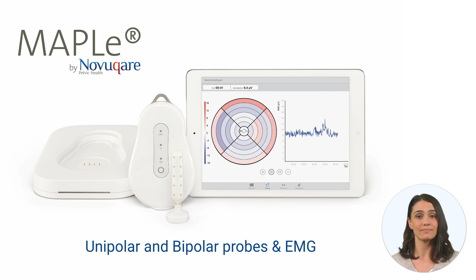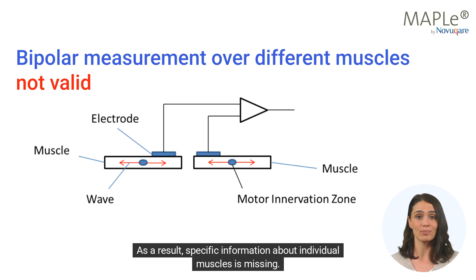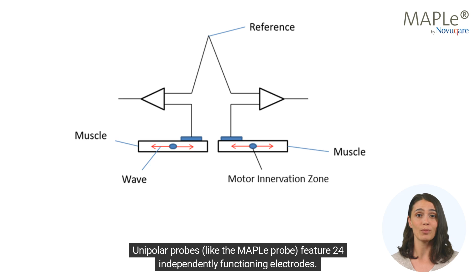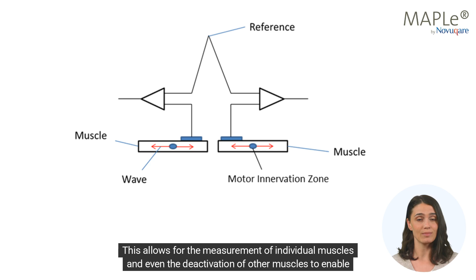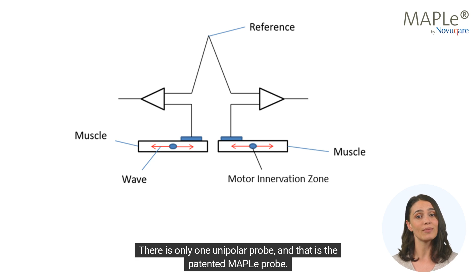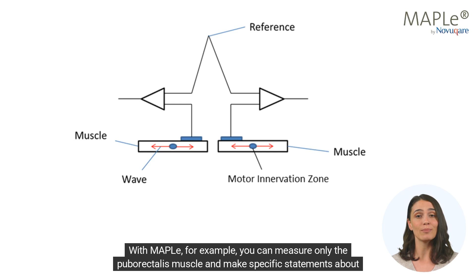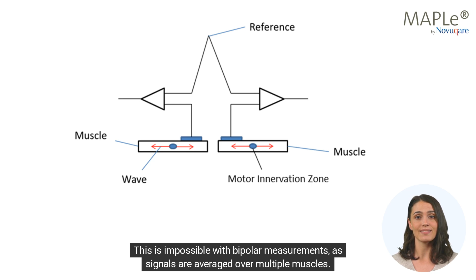A key difference between MAPLe, a unipolar probe, and traditional bipolar probes. Bipolar probes have two electrodes that measure signals from different muscles and calculate an average value. As a result, specific information about individual muscles is missing. Unipolar probes, like the MAPLe probe, feature 24 independently functioning electrodes. This allows for the measurement of individual muscles and even the deactivation of other muscles to enable more targeted diagnostics. There is only one unipolar probe, and that is the patented MAPLe probe. With MAPLe, for example, you can measure only the puborectalis muscle and make specific statements about muscle activity. This is impossible with bipolar measurements, as signals are averaged over multiple muscles.